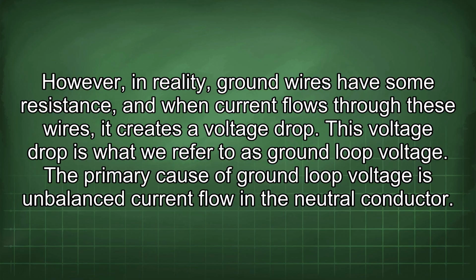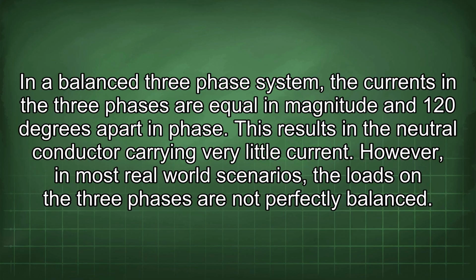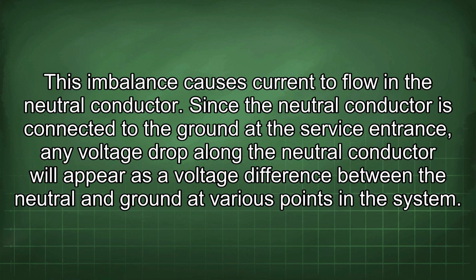The primary cause of ground loop voltage is unbalanced current flow in the neutral conductor. In a balanced three-phase system, the currents in the three phases are equal in magnitude and 120 degrees apart in phase. This results in the neutral conductor carrying very little current. However, in most real-world scenarios, the loads on the three phases are not perfectly balanced. This imbalance causes current to flow in the neutral conductor.